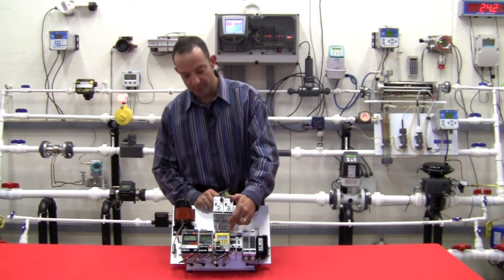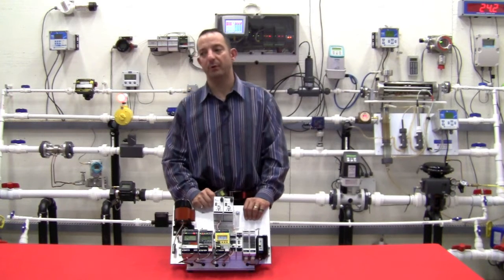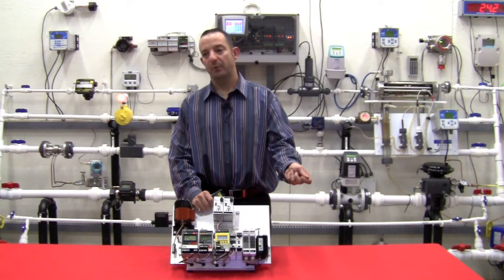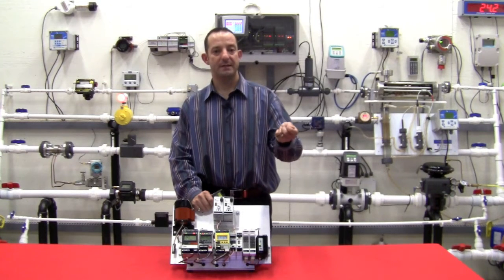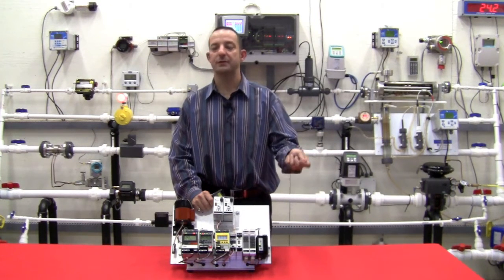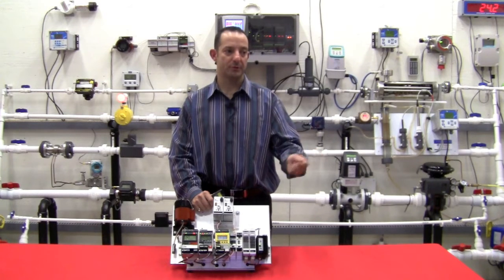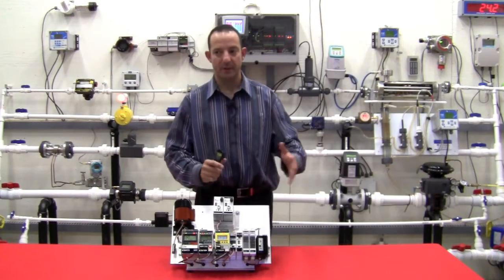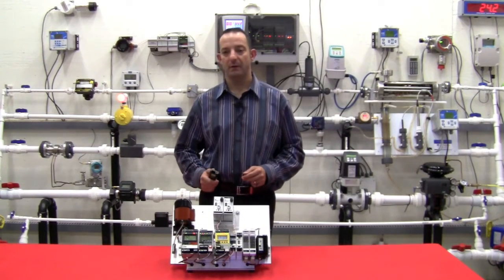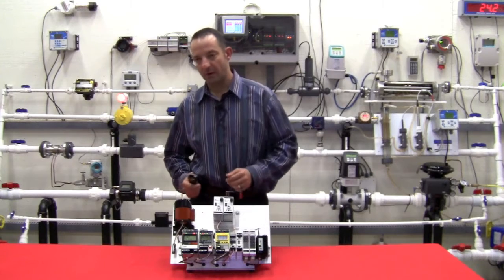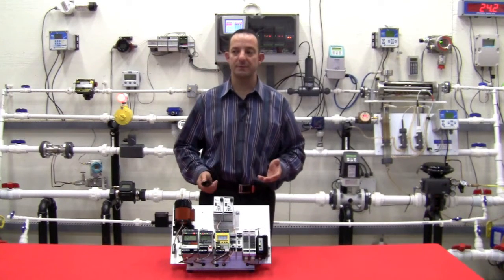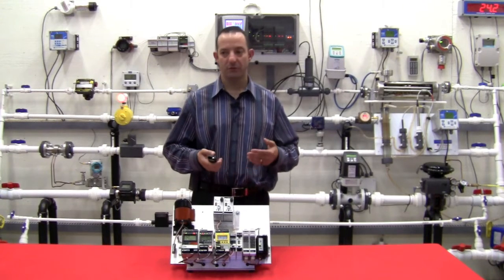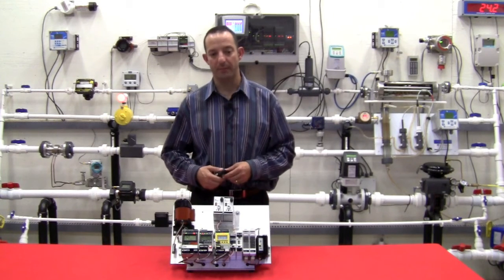We also give you the capability for sensor trimming on temperature inputs. So you can stick a thermocouple or an RTD in a temperature standard bath used in the plant for temperature system calibration and actually adjust the input of the alarm trip to match that plant standard. So even though our front end on all these devices is extremely accurate, you can always tune it or trim it to match another standard in the plant that's agreed upon.